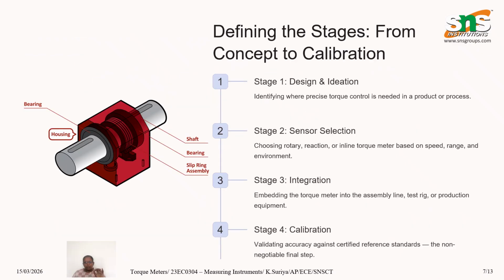So the successful use of the torque meters involves several stages. The first stage is design and ideation, where engineers identify the areas requiring precise torque control. The second stage is sensor selection, where an appropriate torque meter is chosen based on the speed, torque range, operating conditions, and application requirements. The third stage is integration, where the torque meter is installed in the machinery, production lines, testing equipment, or assembly systems. And the final and the most important stage is the calibration stage, where it ensures that a torque meter provides accurate measurements by comparing its readings with certified reference standards. Without proper calibration, measurement accuracy cannot be guaranteed.